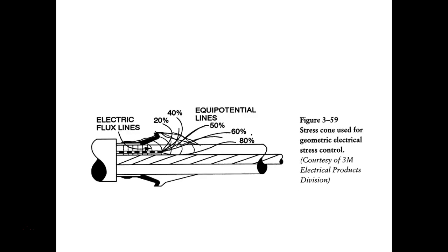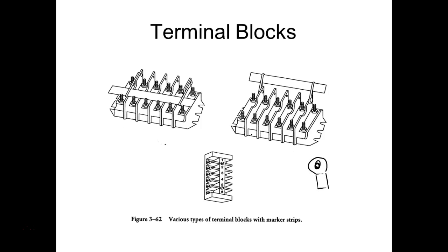So these are terminal blocks. But inside a PLC, and also a lot of your terminal boards, they're going to compression type, which will have a plate or something inside there, attached to maybe a screw or an Allen head screw. Then you go down here, and this is inside a chamber. You could put solid wire or stranded wire in here, and when you screw this down, it brings this plate down. These work different ways. I've seen them angled with a flap, and we'll look at those. More of your terminal boards are going to that technique, so you don't have to put terminals on them, which makes your terminations a lot faster.